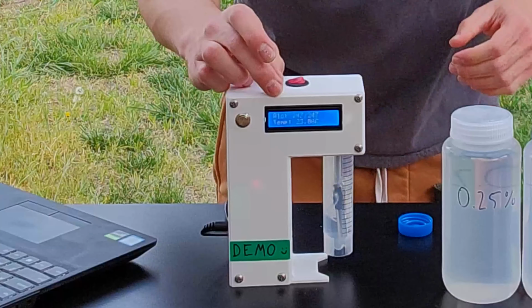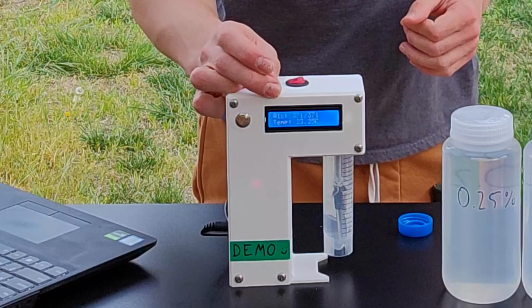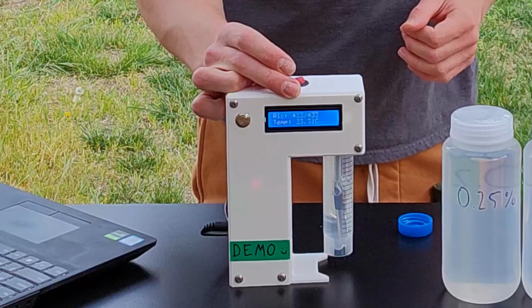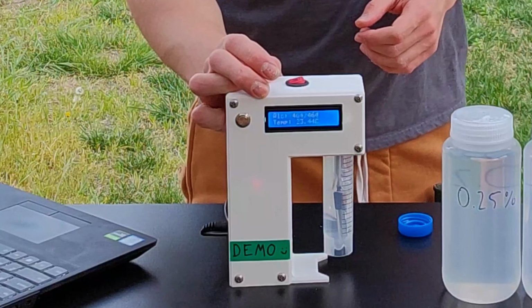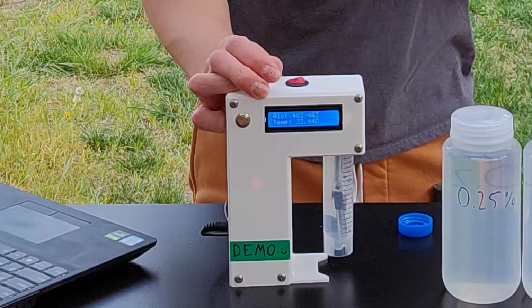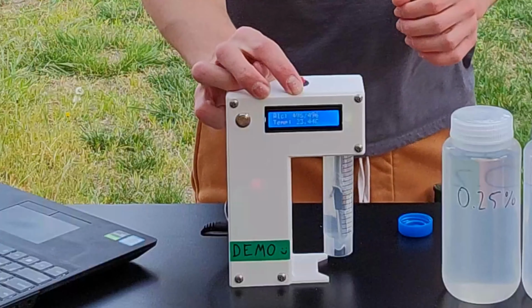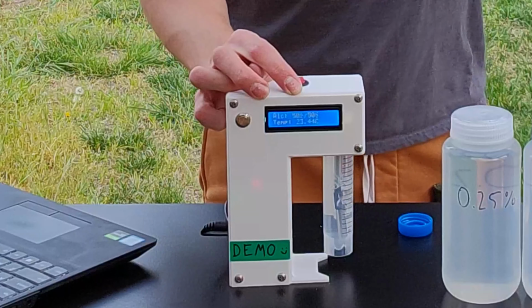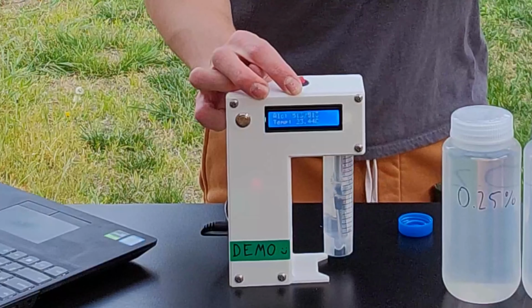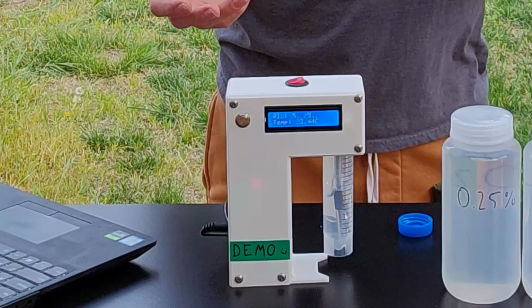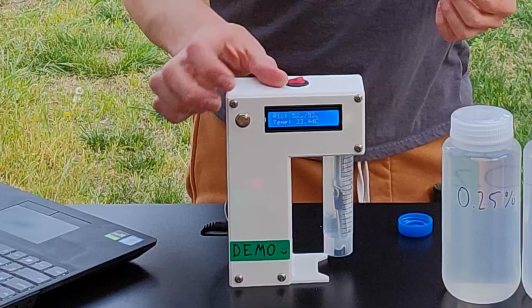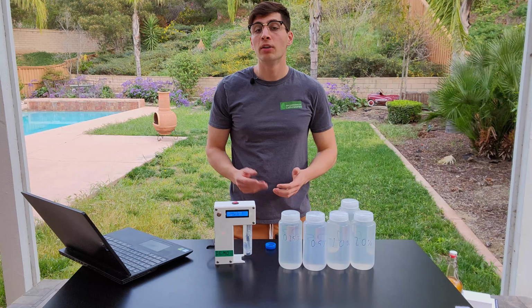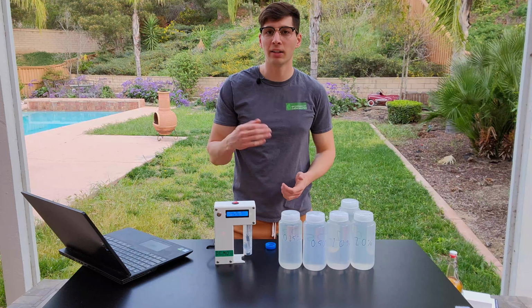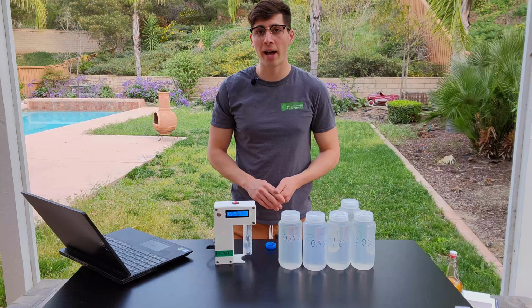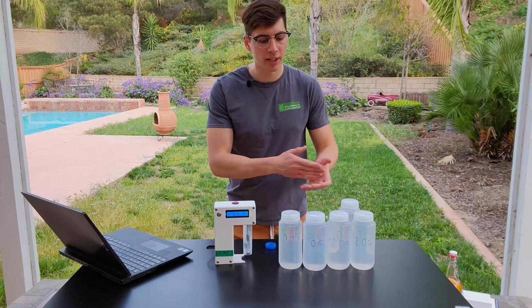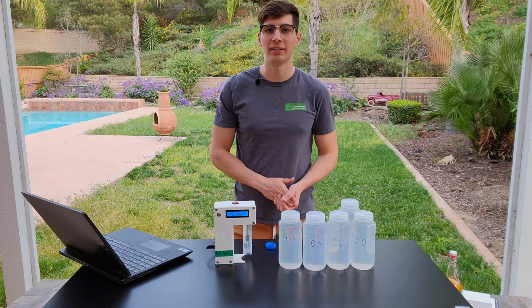and you can see the reading on the left should rapidly climb, and the reading on the right should climb as well. So the reading on the left is the current raw reading of the device. The reading on the right is sort of a ratcheting mechanism to record the highest reading on the device within a given period of time. To reset the reading on the right, you can press and hold the silver button. So the very first reading is going to take a little bit more time, maybe closer to 1.5 minutes or 2 minutes, but all of the other samples should take about 30 seconds to a minute to get their readings.